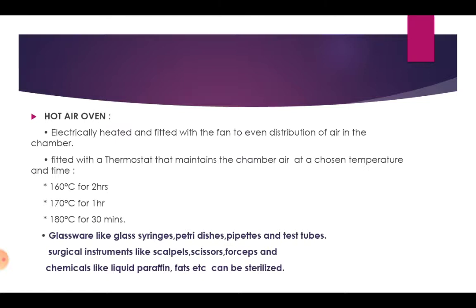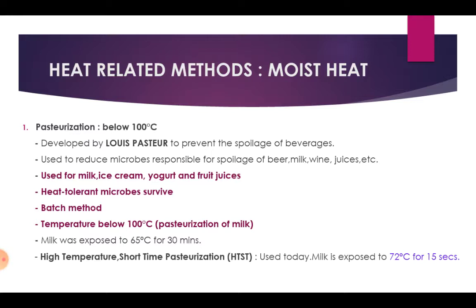Hot air oven. Electrically heated and fitted with a fan for even distribution of air in the chamber. Fitted with a thermostat that maintains the chamber air at a chosen temperature and time: 160 degrees Celsius for 2 hours, 170 degrees Celsius for 1 hour, 180 degrees Celsius for 30 minutes. Glassware like glass syringes, petri dishes, pipettes, and test tubes, and surgical instruments like scalpels, scissors, forceps, and chemicals like liquid paraffin, fats, etc. can be sterilized.